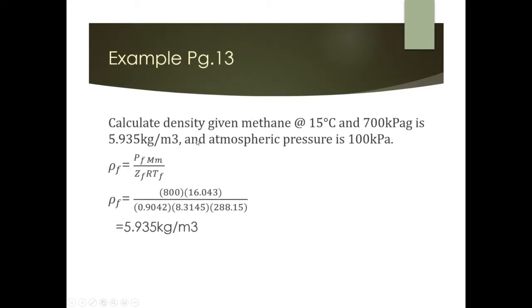Example: calculate the density of methane at 15°C and 700 kPa, with atmospheric pressure of 100 kPa. The pressure at flowing conditions is the sum of the two pressures. The compressibility factor, gas constant, and temperature in Kelvin — remember to convert Celsius to Kelvin — are all plugged into the formula to get the density at those conditions.